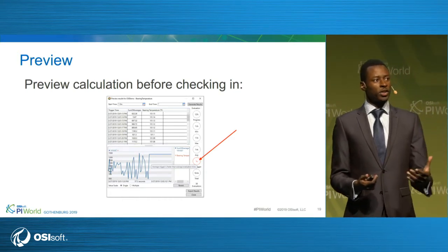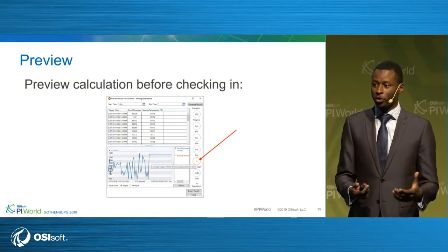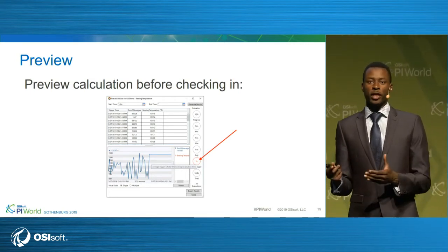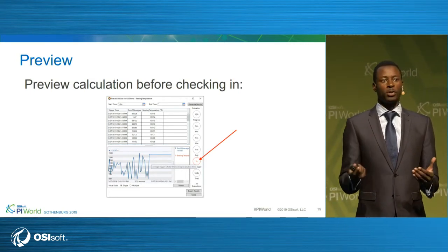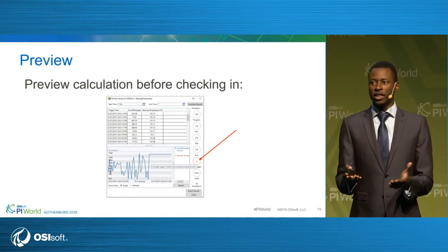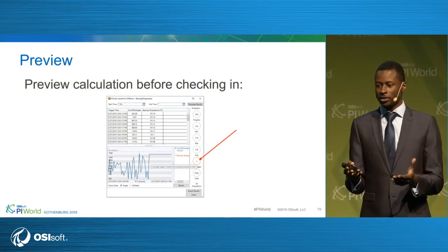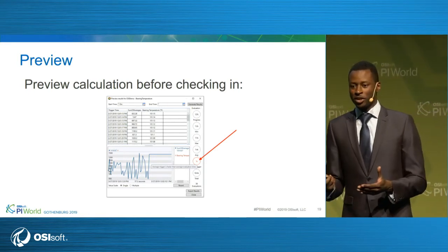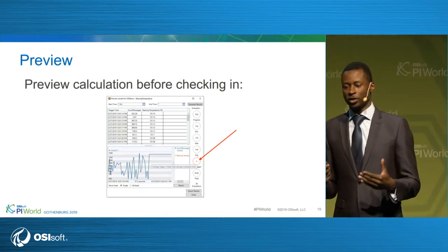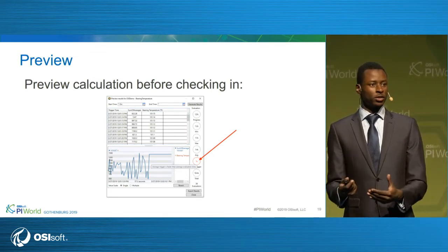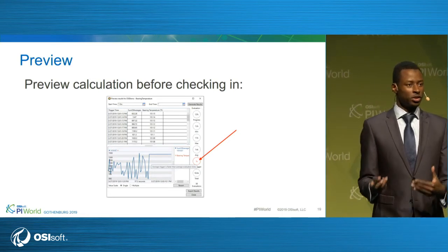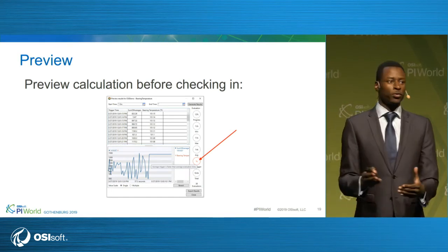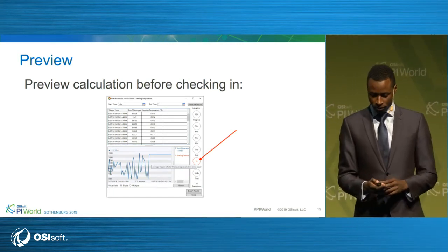So you can preview the calculation over a set time period which you're interested in. You just define the start time and the end time, and it's going to use the inputs to calculate all the outputs over that period of time. So this now allows you to see how the analysis is going to perform once you backfill data. I get customers come to me and they're like, oh, the backfilling, I do it, and it doesn't work how I expected it to, and I end up having to delete the data and try again. Well, first of all, come here and preview your calculation before you do your backfill. So that's the advice there.